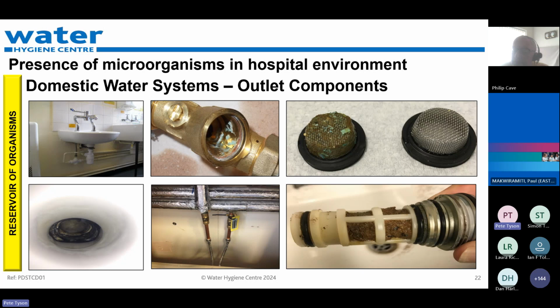But as you can see in these photographs, there are a lot of areas within these systems where biofilm can form, and biofilm can harbour any waterborne pathogen: amoeba, Legionella bacteria, etc. We've just highlighted a drain, and where water does not flow freely down the drain, it can splash back and cause a biofilm to develop. There's also an efflux, a plug hole belch, if you will, where water can be trapped and gurgle, spurting back out coupled with the biofilm or water from within the trap. And strainers and filters can become areas where biofilm can be established, and non-WRAS approved materials are a great potential nutrient for biofilm and bacteria.